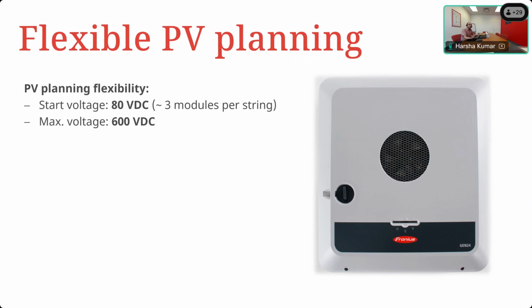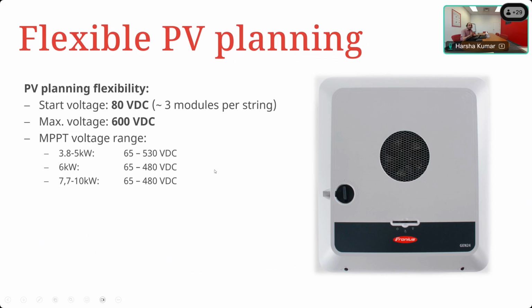But for now, please always keep in mind when you design this that the maximum input voltage is 600 volts DC. So your open circuit voltage, even at the lowest temperature you would expect to see at the site, will need to stay under this if you intend not to damage the inverter. Now the MPP, what we saw there was basically the operating range, if you will. But outside of that, you also have to keep in mind that the string voltage is geared to be worked at for the MPP voltage rather than the open circuit voltage, which is why the MPPT voltage range is also just as important.